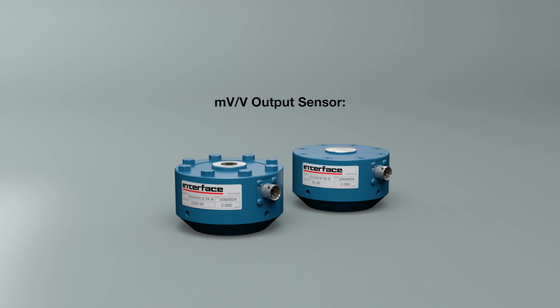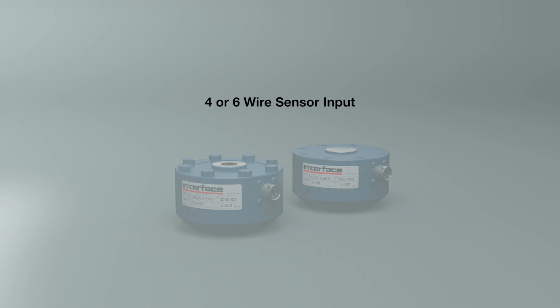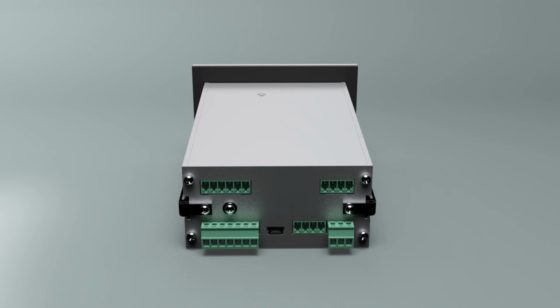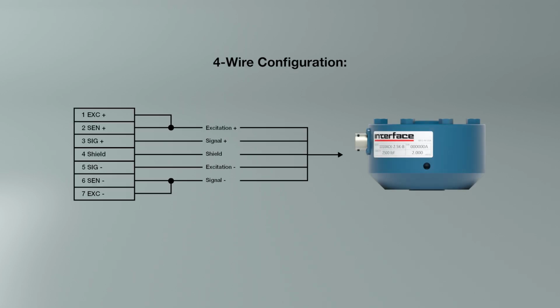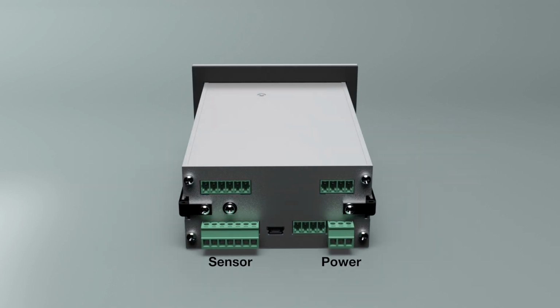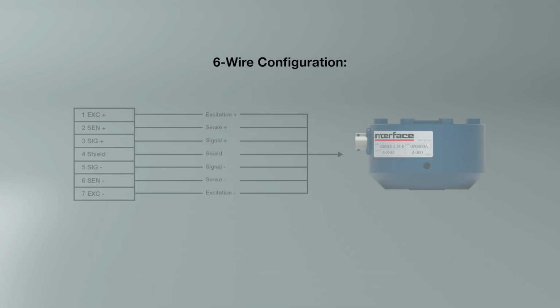The sensor. The 9825 indicator requires millivolt per volt sensor input for operation. The 9825 can accept 4 or 6 wire sensor input. The sensor is connected to the 9825 via a 7-position screw-down terminal connector. If the 9825 is used in conjunction with a 4-wire configuration sensor, the excitation leads must be jumped to the sense terminals for proper operation. Use the screw-down terminals to secure the sensor leads to the 7-position connector in either the 4-wire configuration or the 6-wire configuration, depending on the sensor type.